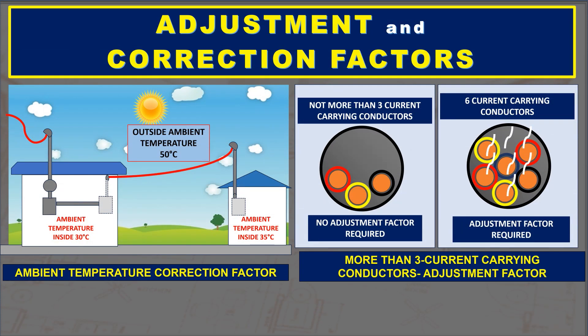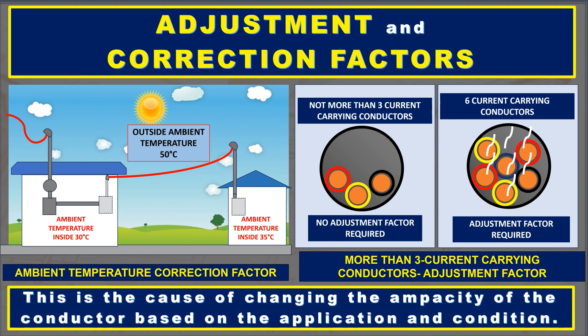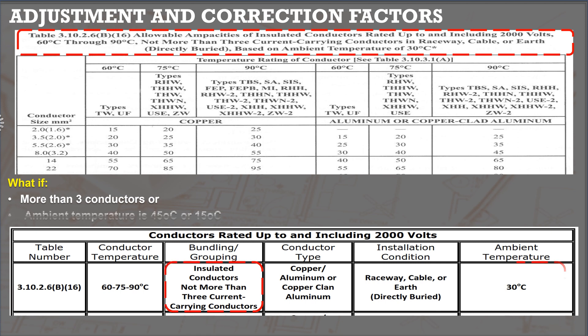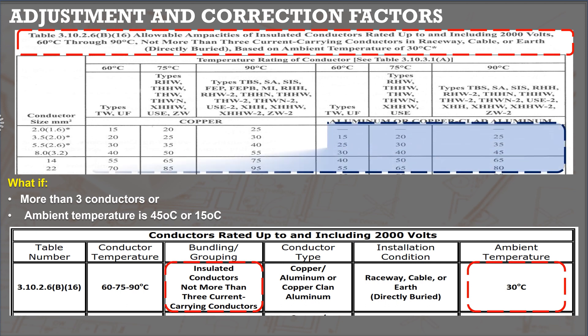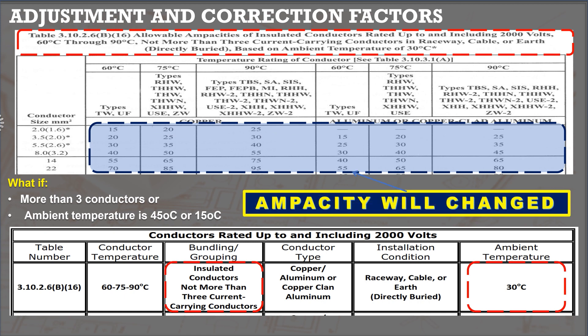What are adjustment and correction factors? Two factors can reduce conductor ampacities: ambient temperature and bundling of more than three current-carrying conductors. Correction and adjustment factors change the ampacity of the conductor based on application and condition. What if conductors are installed in one conduit with more than three current-carrying conductors, or if the ambient temperature is more than 30 degrees Celsius? The ampacity given in the table will change — it can become higher or lower.